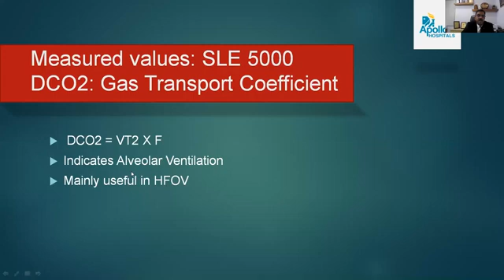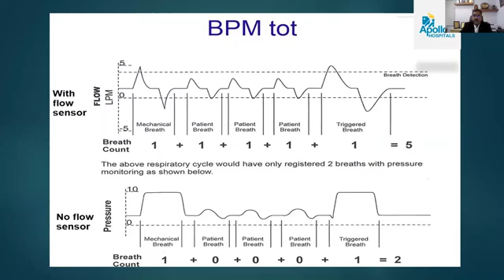For the total breaths per minute, if it is with the flow sensor, each breath, mechanical and patient breath, is calculated and gives you the total breath. If there is no flow sensor, then the ventilator will calculate only the mechanical breath, and it cannot sense the patient breath. So when you see the breaths per minute, you should know whether you have put the flow sensor on or it is not there.